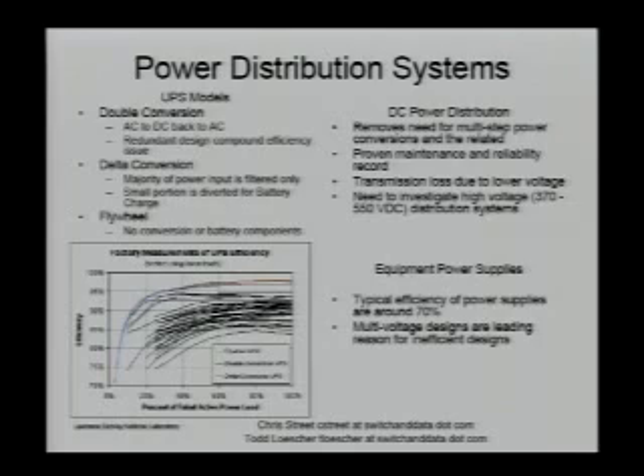The downside of DC power is that you lose some during transmission due to the lower voltage, negative 48. We're seeing data centers looking at high voltage to negate that low-voltage transmission loss, pulling out high voltage anywhere from 370 to 550, depending on the vendor's packages, all the way out to the distribution at the racks.